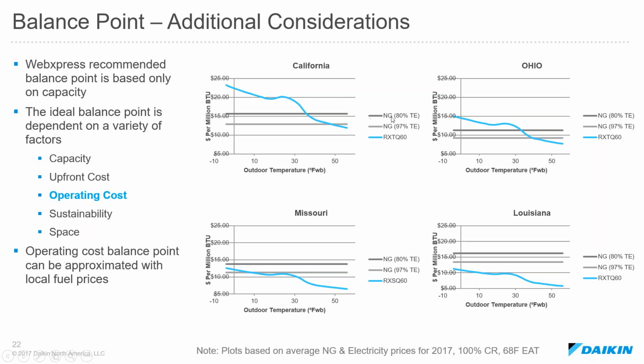So you see we have two different efficiency furnaces in the gray, and then we have the RXTQ 60, or that should say RXSQ, that's an error there. And then we're plotting that in dollars per million BTU. So how much energy, or how much money does it cost me per million BTUs? And you see the gas furnace is staying constant. It's not affected by the ambient temperature, but as it gets colder outside, it starts to cost you more per unit of energy to run that heat pump.